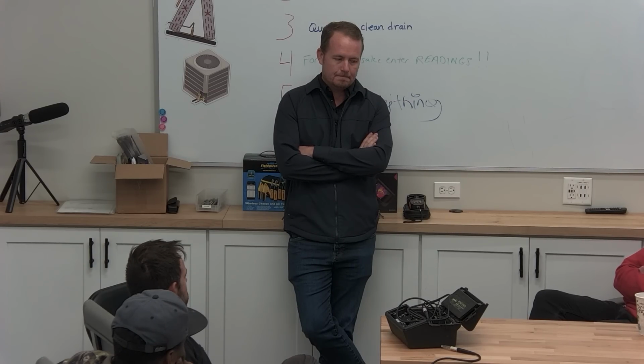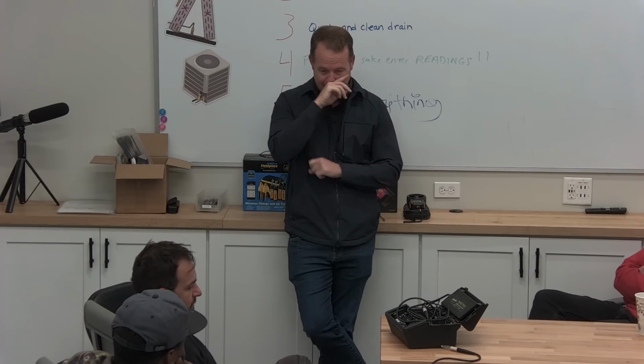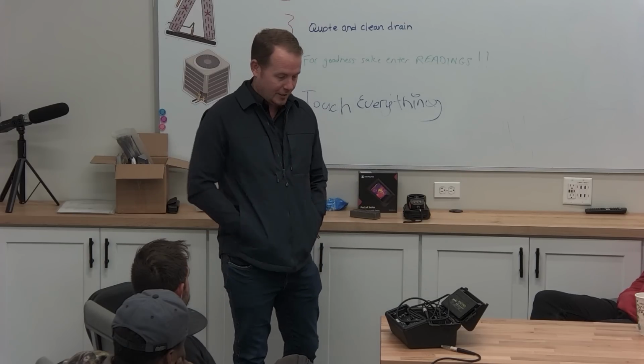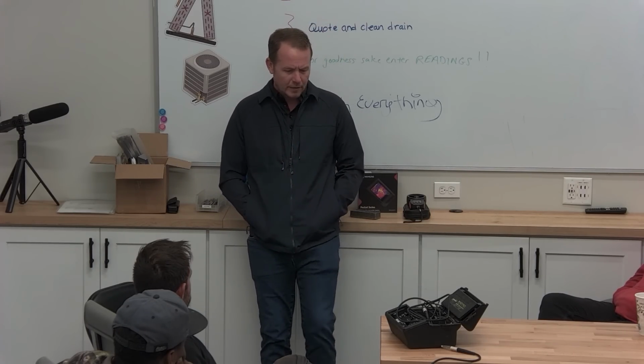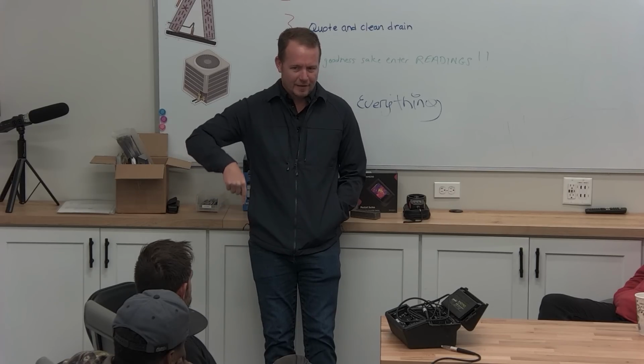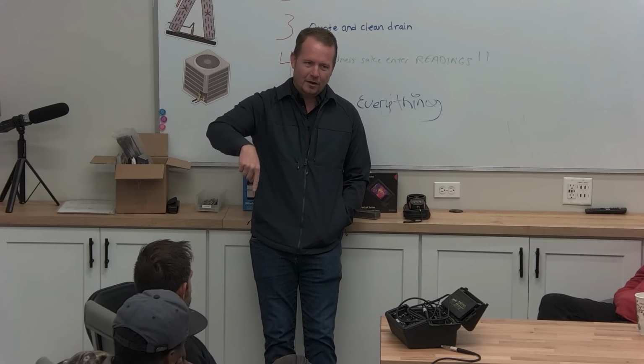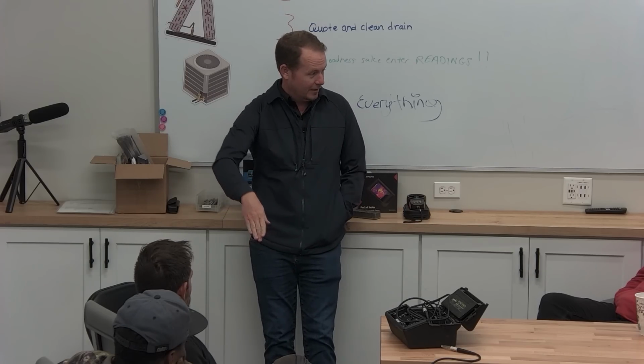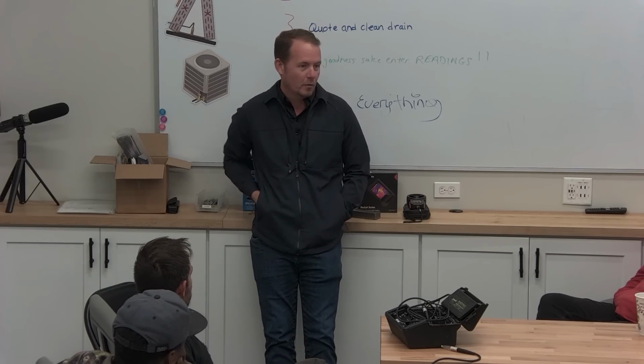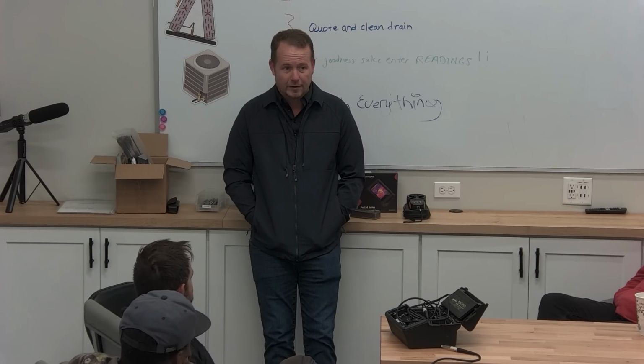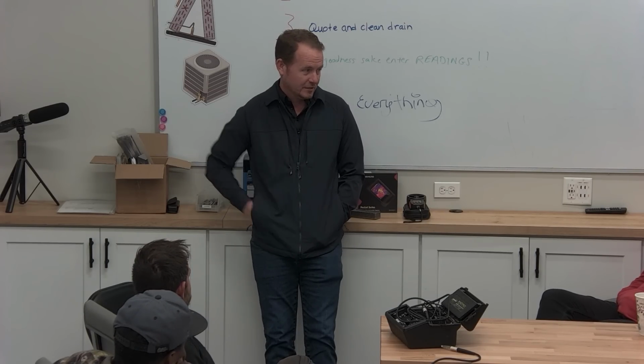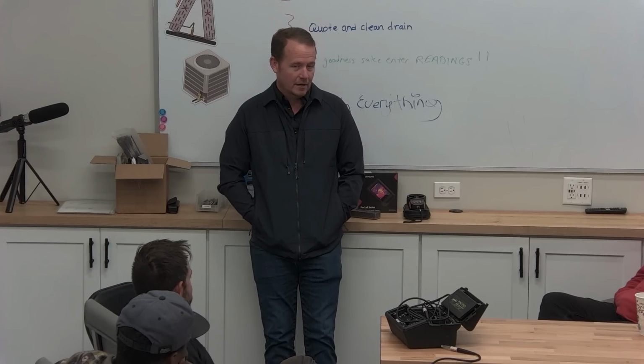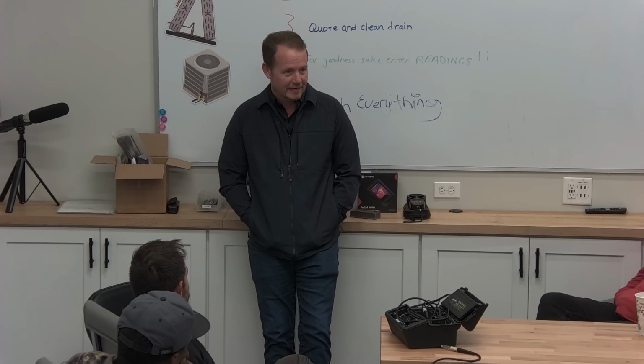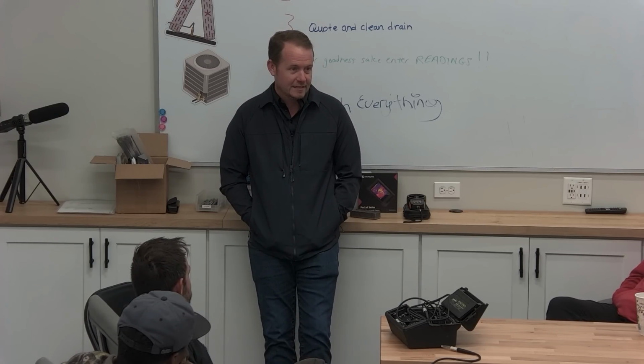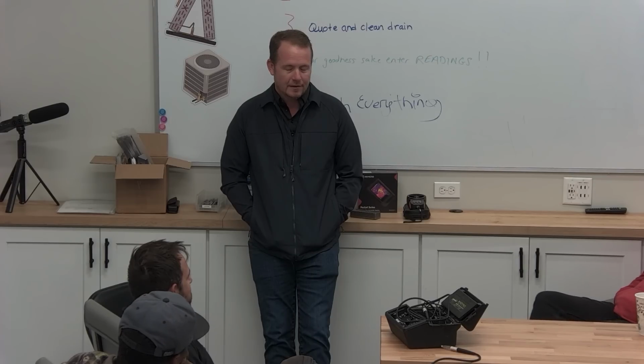One job Jesse and I did years ago, when we were first testing the predecessor to the Inficon, we went to a job with a persistent leak and found one in the evaporator coil. But then we saw a big white spot on the ground underneath the drain line, right over the copper where it went into the ground. What causes that? Bleach. The customer was pouring a lot of bleach down the drain, and it wasn't just a little, it clearly stained the mulch. We didn't know what they were trying to solve for, but we figured we'd better dig that up. Sure enough, we dug it up and found a significant hissing leak in the drain, in the chase.